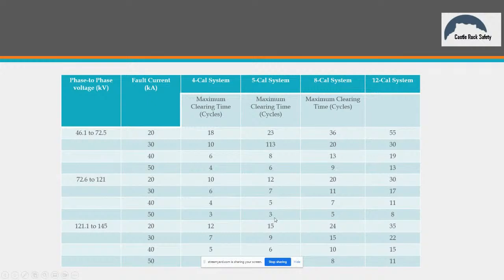It's the same thing. Your fault current's going up, and then you've got some clearing times, and you'll see that again about 12 calories is as big as it gets, right? Now, the difference here is obviously our working distances are going to change because we're not going to be gloving any of this. All this is going to be done working with a stick, right? We're not going to be 15 inches away here.